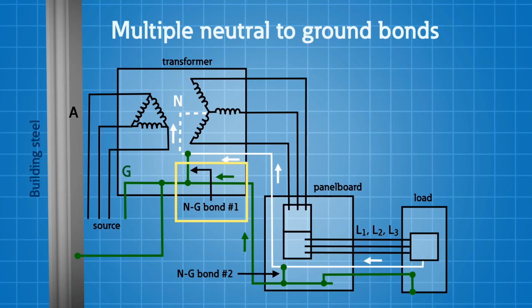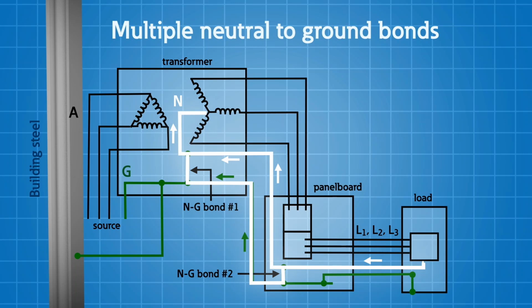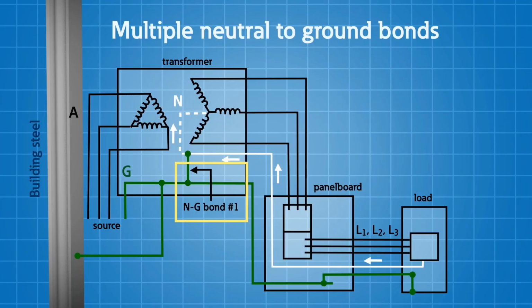Why do we only connect ground once? Well, if we incorrectly ground the neutral downstream of the first connection, here's the problem. Load current will return on both the neutral and the ground conductor, which is connected to all the metal parts in the system. For that reason, current will divide at the subsequent neutral to ground bond, and load current will flow in the ground. We absolutely don't want current to flow in the ground conductors unless there's a ground fault. Having a single neutral to ground connection ensures that this will be the case. In this next section, we will explain how this applies to larger three-phase transformers.